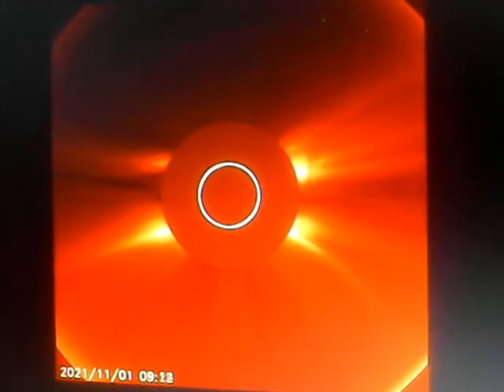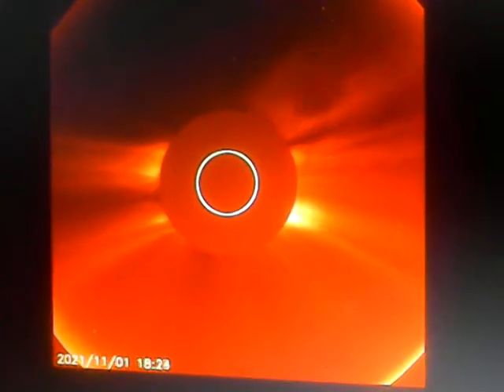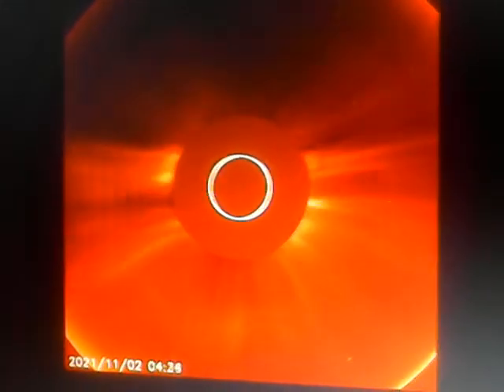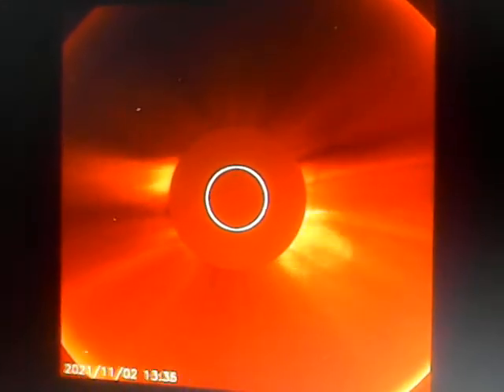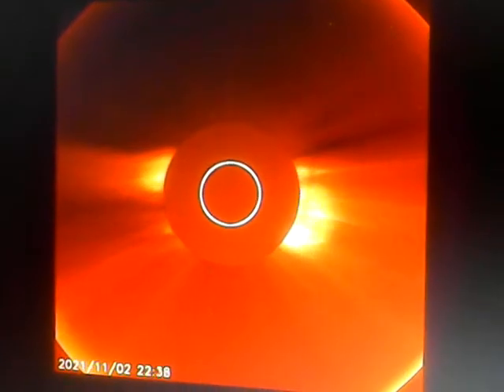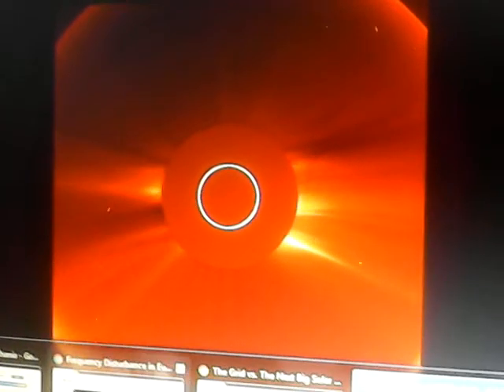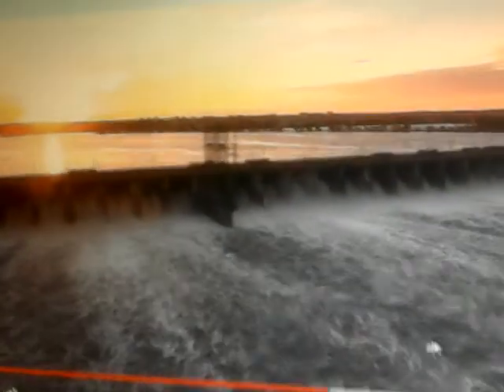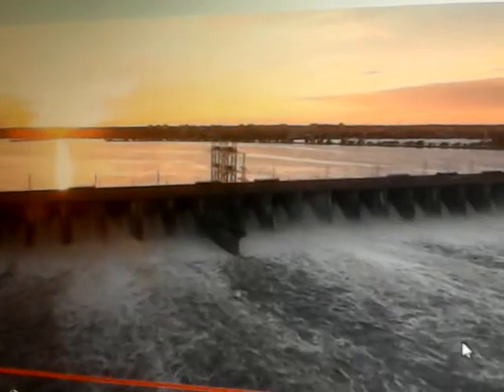When this happened in Quebec, the grid voltage became unstable, causing protective relays to disconnect 5 high-voltage transmission lines, including one from a hydroelectric facility. As the hydroelectric facility was disconnected, it experienced a rapid loss of load, meaning its power had nowhere to go, which caused the voltage to suddenly increase, damaging 2 step-up transformers as a result of excessive heating.